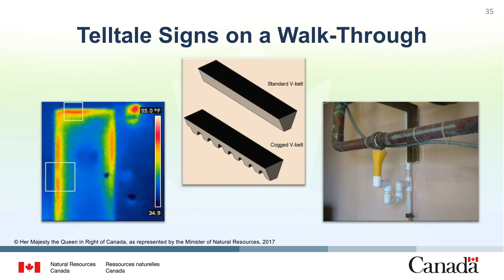Next, we look at the belts through the entire facility and we see that they typically use V-belts. If they use cog belts, they could save as much as 5% due to lack of slippage and less resistance. And in the last photo here, we have a situation where there was a water leak, and rather than fixing the leak, the staff have used their ingenuity to collect the leak so that it goes down the drain.